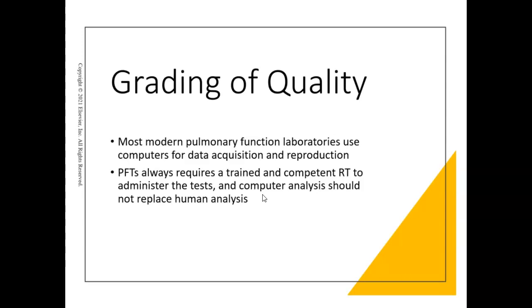That's the minimum standard. It is best practice, though, in a lot of very high quality pulmonary function labs to do that 3-liter syringe calibration before every single patient. So if they have 5 patients scheduled that day, they will do that calibration before each of those patients does their PFT testing.